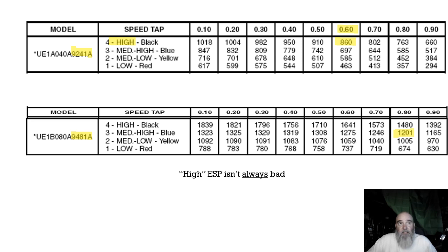The lower example shows an 80,000 BTU furnace with a 4-ton drive. And if we happen to be on medium high speed at 0.8, that could be a perfect match for a 3-ton system if you're a big advocate of 400 CFM per ton. So when it comes to blower sizes, just because it is a specific size doesn't mean we have to run it at that capacity. It's not uncommon to see a 4-ton drive moving airflow that is significantly less. The opposite is seldom true, though, although not completely out of the realm of possibility, as shown in the 2-ton drive at the top of that screen.